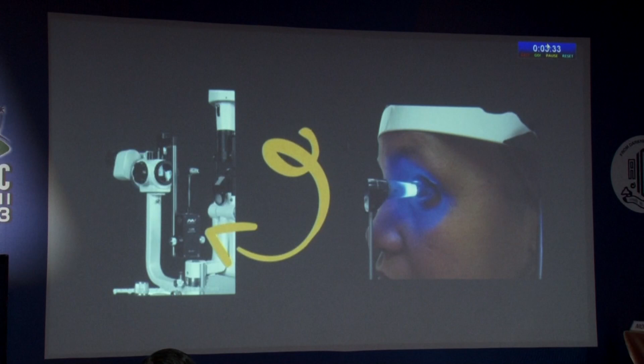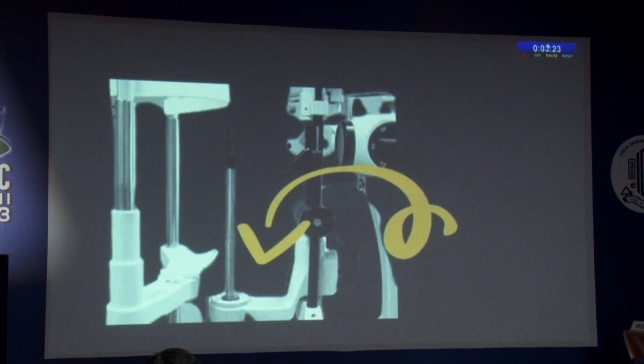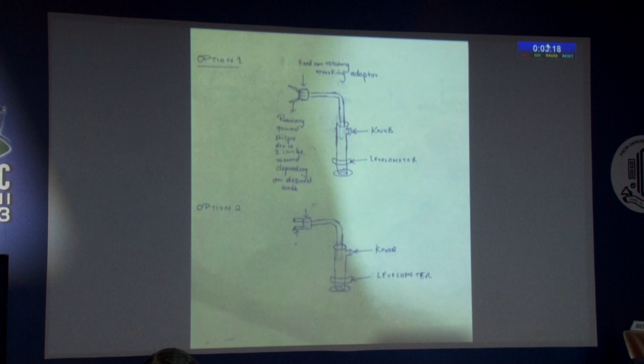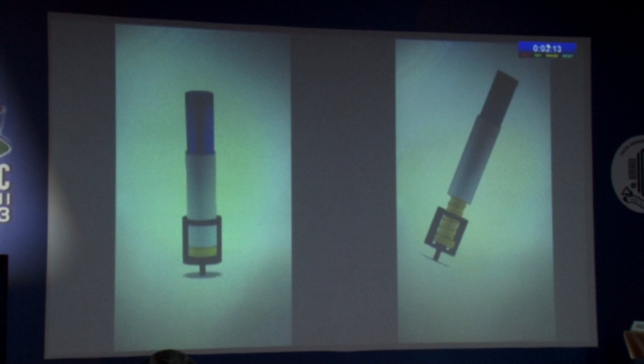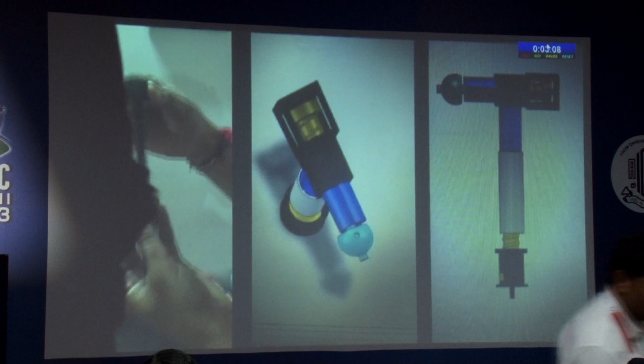We took inspiration from the Goldmann applanation tonometer, which goes and indents the cornea of the patient, and the patient is not hesitant at all. We decided to use the calibration slot, which is universal in every slit lamp, for our slit lamp based toric marker. This was the first hand-drawn diagram of our toric marker. We further started doing 3D printed models. As you can see, the 3D printed models became bulkier every time. Thus, we finally settled with a shaft within a shaft, that is the IV stand design.